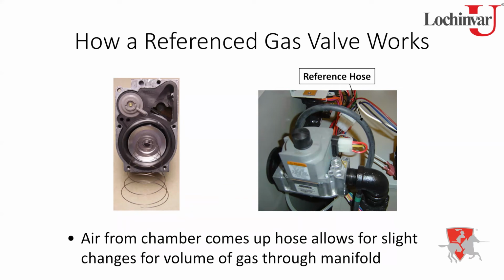So basically what you're telling me is maybe if I get a weird wind coming onto an intake or something like that, I can compensate for that little bit of extra air up to a certain point and not throw my combustion off too much, right? Exactly, and that's all it's there for. Basically just to help maintain that balance.